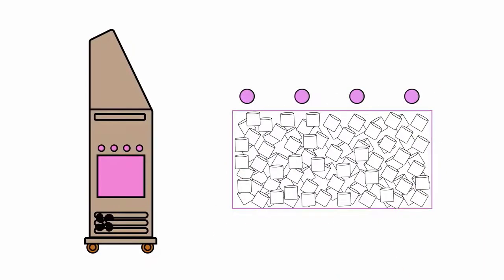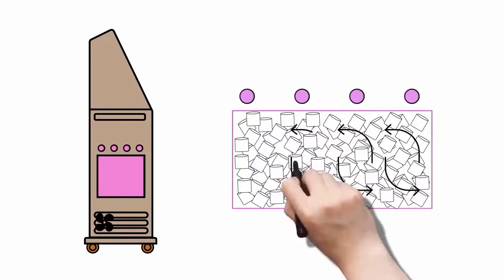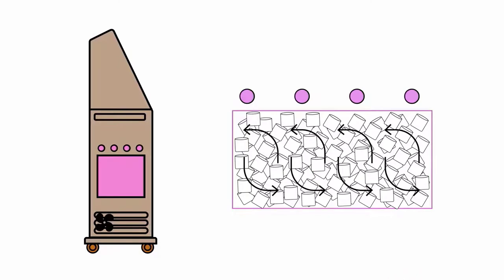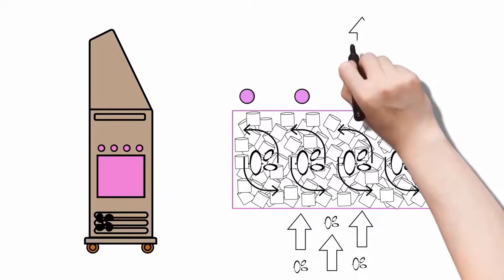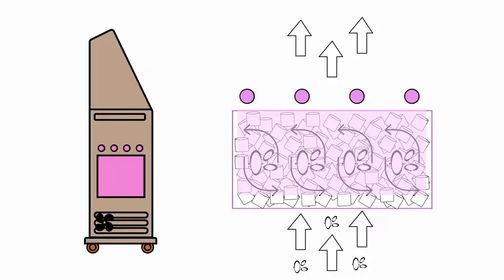This box is filled with hundreds of small quartz cylinders. The air flows through the box at high speed, and any and all microbes in the airstream are caught in the matrix of cylinders. The cylinders act as a maze, where the microbes must take a long turbulent path in order to make it through. While the microbes are trying to find their way out of the maze, they're being hit with ultraviolet light. The quartz matrix lets ultraviolet light and air pass through, but doesn't allow microbes to pass through.